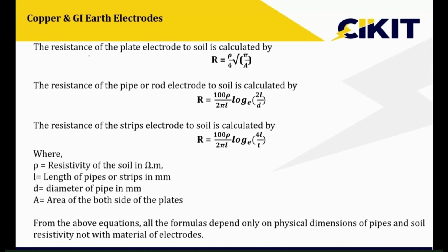This is the formula provided by the standard for calculating the resistance value of different configurations. The first one is plate earthing, the second is pipe or rod, and the third is strips. If you observe closely, in all the formulas we consider rho, the resistivity of the soil. So the resistivity of the soil plays an important role, and all other parameters are related to the dimensions of the electrode. Here we are not at all considering the material of the electrode. It can be copper, GI, cast iron, or aluminum, anything. But we do not consider the material because in earthing, the material does not come into the picture, because it is electrolytic resistance. The impact of the resistance of the material is much lesser, whereas the impact of the soil resistivity is much higher. That is the reason that in all the formulas we consider the resistivity of the soil and not the resistivity of the material.